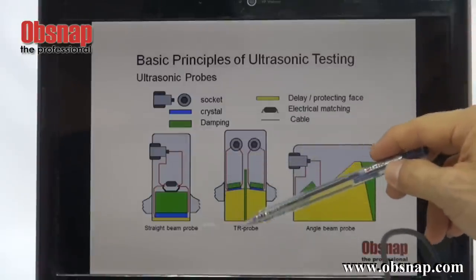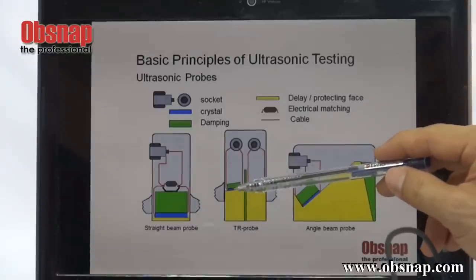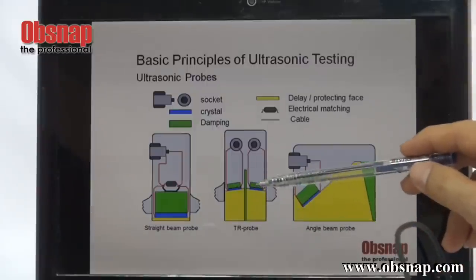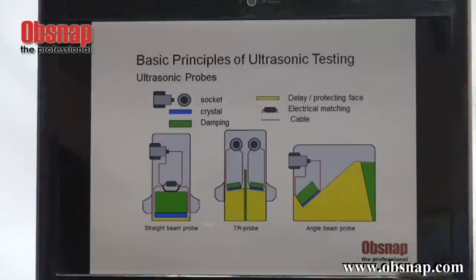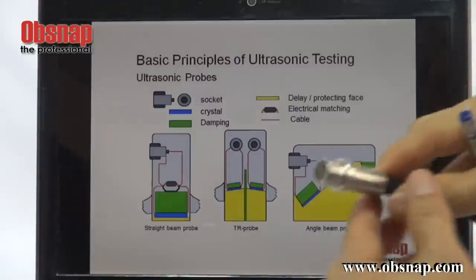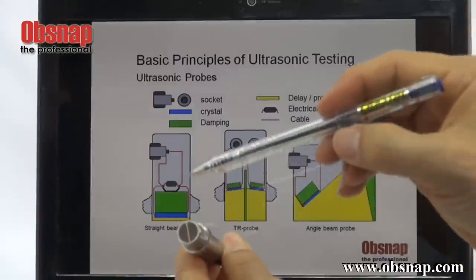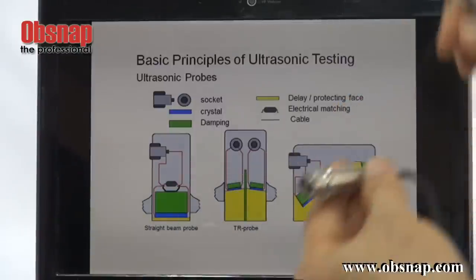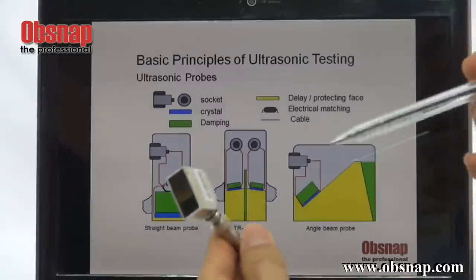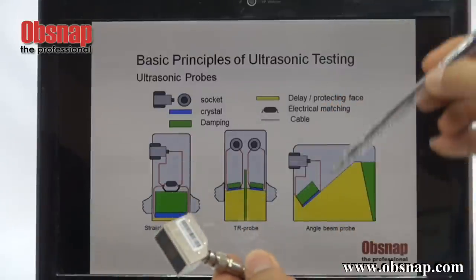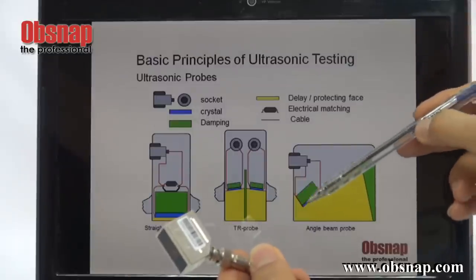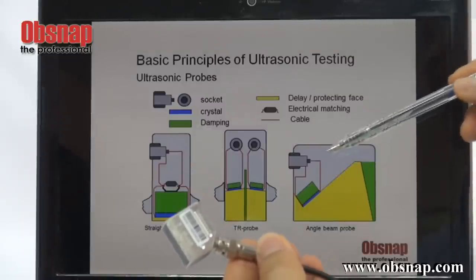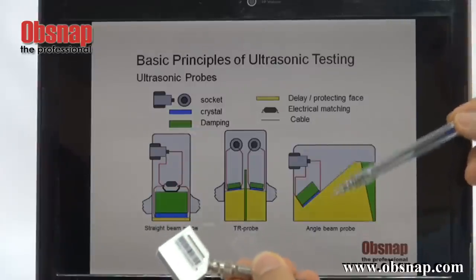This is called the Twin Crystal Probe — one crystal is actually to transmit the sound wave and the other is responsible to receive and detect the reflected echo. And this is the angle probe. It is called an angle probe because the crystal is actually sitting at an angle, which allows detection of very thin material — down to probably 5 mm or even slightly thinner.